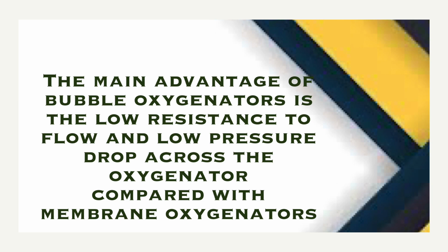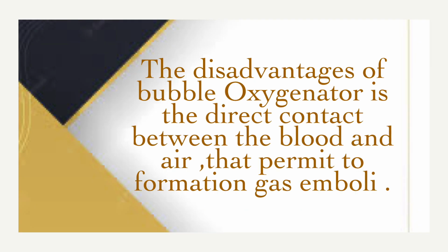The main advantage of the bubble oxygenator is the low resistance to flow and low pressure drop across the oxygenator compared with membrane oxygenators. The disadvantage of the bubble oxygenator is the direct contact between the blood and air, which permits the formation of gas emboli.